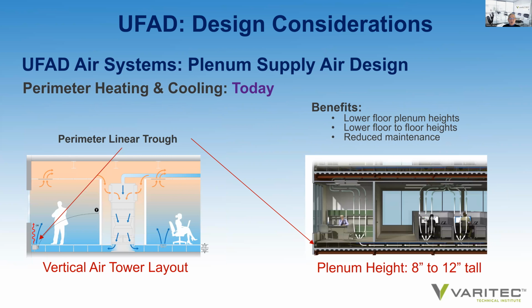So this is how they look in design. And as you can see, that air is injected through a vertical air column, an air handling solution that I'll address later in this presentation, that projects air to the perimeter, whereby plenum pressure drives the cool air to the perimeter troughs, or in heating mode, the dampers to the plenum go to a closed position. The heating element is enabled, and warm air services the perimeter wall via convection.